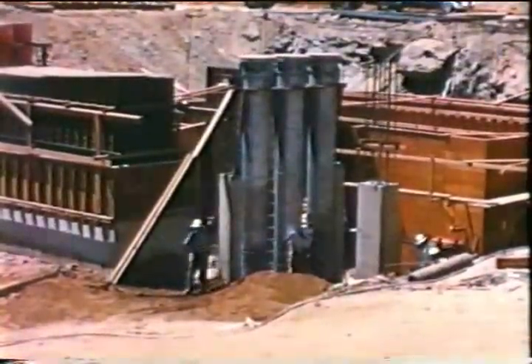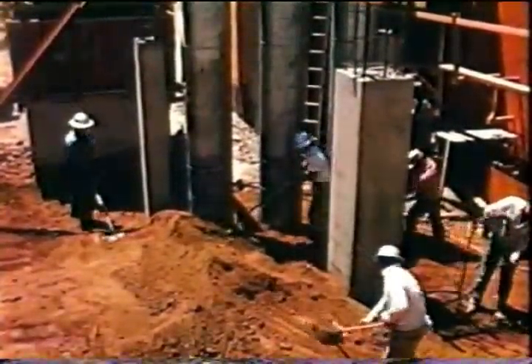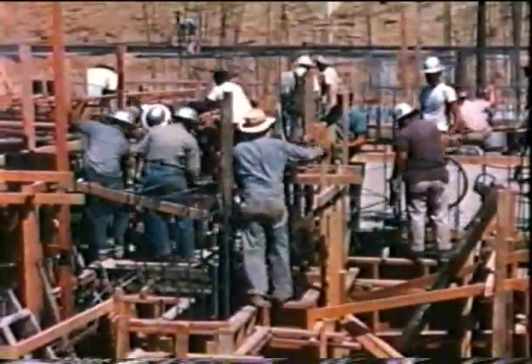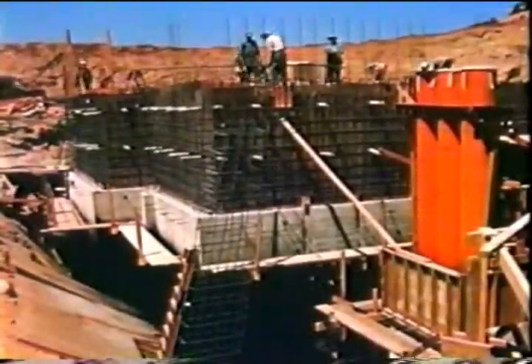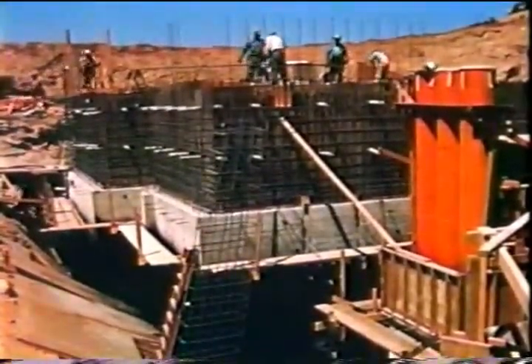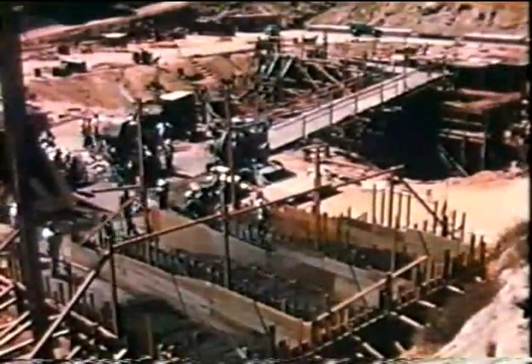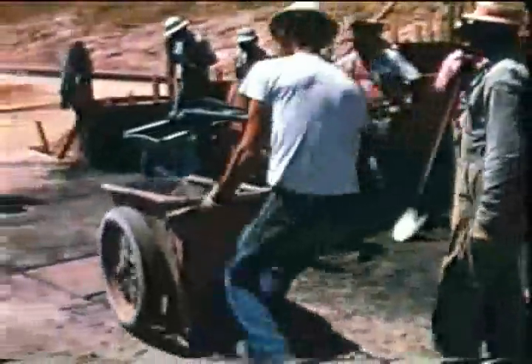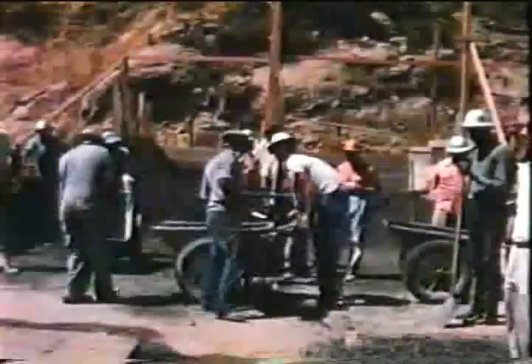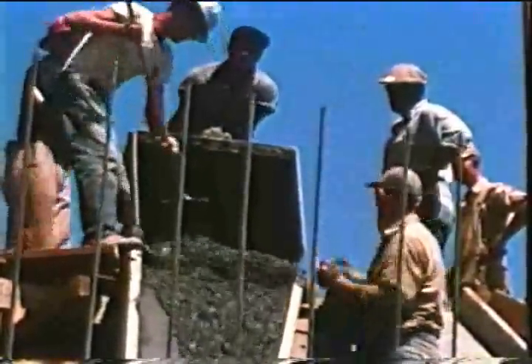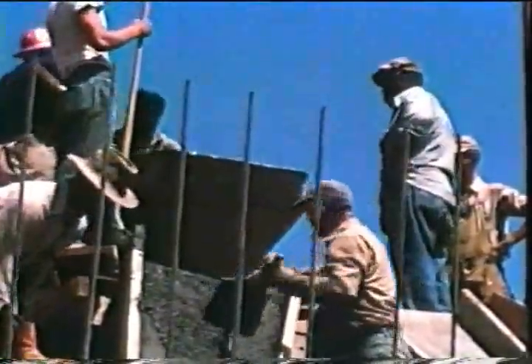Enclosed cells, also beneath ground level, are provided for cleaning and storing fuel elements. A hot cell houses the facilities for examination and disassembly of any radioactive component from the core. The upper 6 feet of concrete of the cavity liner serves as a biological shield. It was made from high-density concrete containing an aggregate of magnetite iron ore. A cylinder of 3 foot thick reinforced concrete formed around the remainder of the cavity liner provides a structural support as well as a radiation and thermal shield.